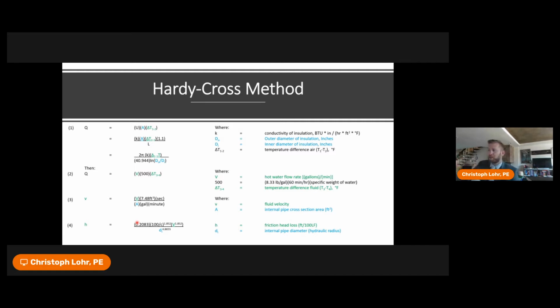Well, one of the things you'll notice is I have a number of the criteria here selected in blue and green. The blue represents actually one variable, which is the diameter of the hot water return system. Again, the hot water return system can be smaller than the hot water supply system because we're not returning 100% of the flow. Typically, we're just returning a portion of the flow. The variables that are in green are the other 4 variables that we have to determine based on variances in pipe size and everything else.